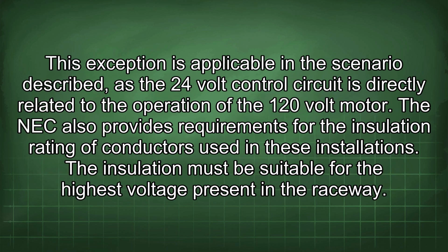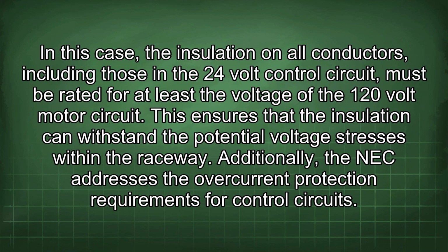This exception is applicable in the scenario described, as the 24-volt control circuit is directly related to the operation of the 120-volt motor. The NEC also provides requirements for the insulation rating of conductors used in these installations. The insulation must be suitable for the highest voltage present in the raceway. In this case, the insulation on all conductors, including those in the 24-volt control circuit, must be rated for at least the voltage of the 120-volt motor circuit. This ensures that the insulation can withstand the potential voltage stresses within the raceway.